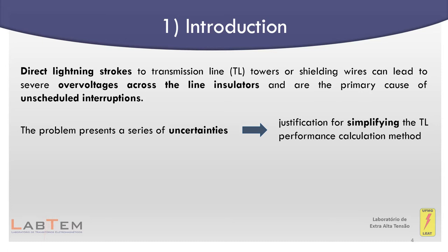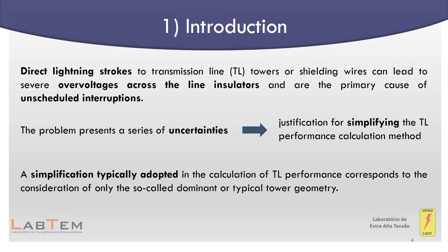A simplification typically adopted in the calculation of transmission line performance corresponds to the consideration of only the so-called dominant or typical tower geometry. This simplification, however, can lead to deviations in the estimation of the line outage rate, especially in cases where the line is composed of more than one type of structure.